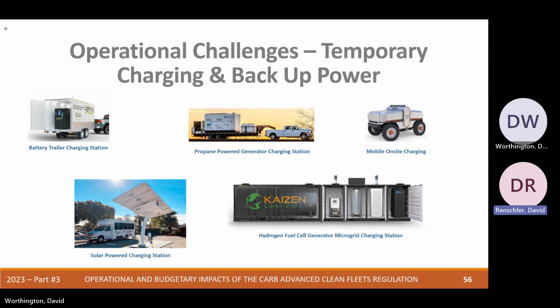In the lower left we have an EV ARC. It's a great piece of equipment if you're going to do level 2 charging, light duty, and charge overnight - solar panels, self-contained battery. However, they don't have a level 3 option right now, and they definitely can't put 548 kilowatt hours back into a bus overnight.